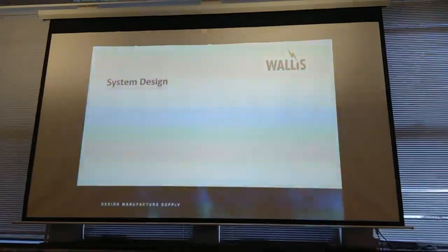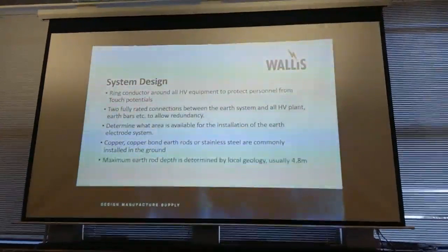Right. So system design basics. Every time we design an earth electrode system, it is solved the same way. We get the HV equipment, we put a ring around it, because at least by doing that, you are protecting somebody who's standing on the ground touching the piece of equipment. You've equipotentialized the ground to the piece of equipment. So if that equipment goes live, you are limiting the potential difference, or the touch voltage as we call it, between you and the piece of equipment. Again, 2 fully rated connections to allow for redundancy.